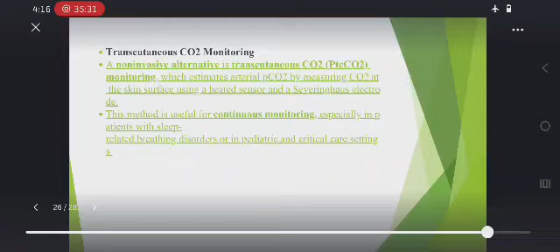The next one is transcutaneous CO2 monitoring. A non-invasive alternative is transcutaneous CO2. Transcutaneous means on the skin surface. The electrode is placed on the skin surface and measures the PCO2. This method gives continuous monitoring, especially in patients with sleep breathing disorders, when the patient sleeps. Transcutaneous CO2 monitoring is mainly used for breathing disorders or in pediatric and critical care settings.